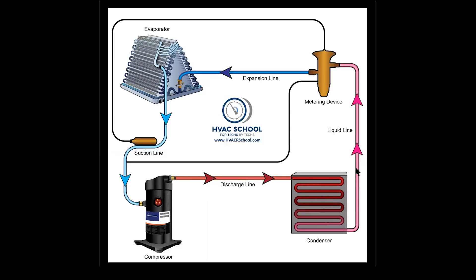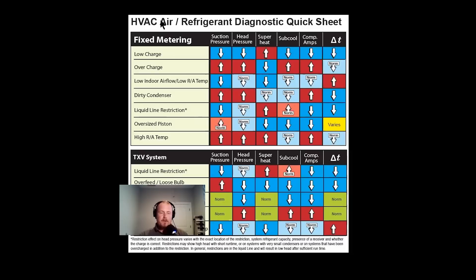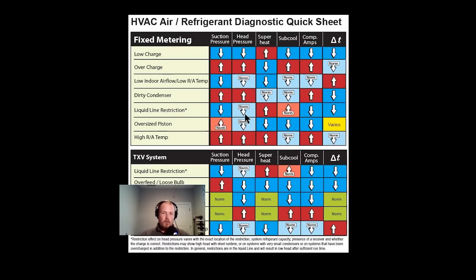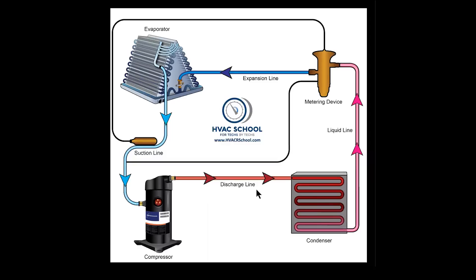They think that refrigerant is going to back up against this restriction and cause high head pressure in the condenser. But if you look at this refrigerant diagnostic quick sheet, it shows right here that your suction pressure will be low — that's sort of the defining characteristic, one of the first things techs always look for. And your head pressure is actually going to be normal to low.